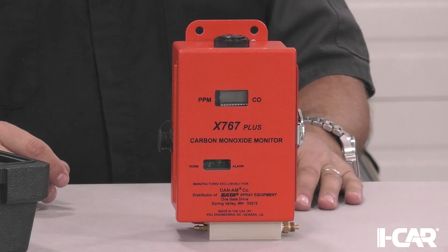It's whatever the intake for your compressor is drawing in, that's where the carbon monoxide could come from. So you have to take a look at where your compressor room is going to be. Because if it's in a small room without ventilation from outside, and it also may have a hot water heater or something that can produce CO, then you'd have to look at ventilating it, running a pipe from outside into the compressor's intake.